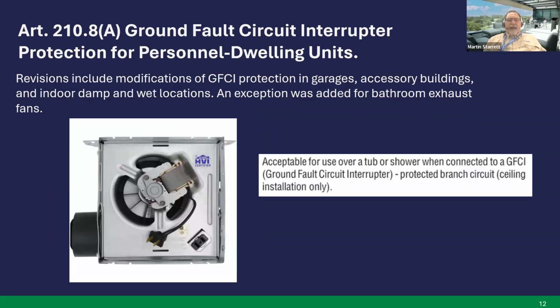Okay, 210.8(A), ground fault circuit interrupter protection for personnel, dwelling units. One thing about 2026, there are no new GFCI requirements for dwelling units. That hasn't happened probably since ground faults were first put in the code. Usually every code cycle they add something new, but this time they didn't. But the revision that we do have includes modification of GFCI protection of garages, accessory buildings, and indoor and damp and wet locations. But basically, those were just a format change. There was no additional language added. They're more in a list view now.